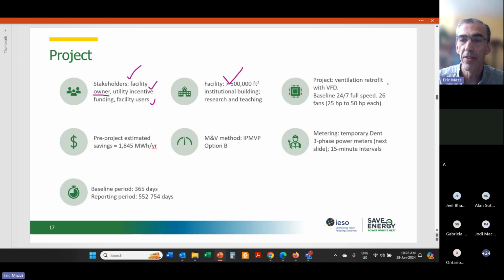The project involved retrofitting fixed speed ventilation systems. There are a bunch, like 26 fans ranging from 25 to 50 horsepower each. They just ran 24/7, 365 days a year at full speed to ventilate. And the retrofit was to put all those fans on variable frequency drives for variable speed control. Before the project, the savings were estimated at about 1845 megawatt hours per year in electricity savings.